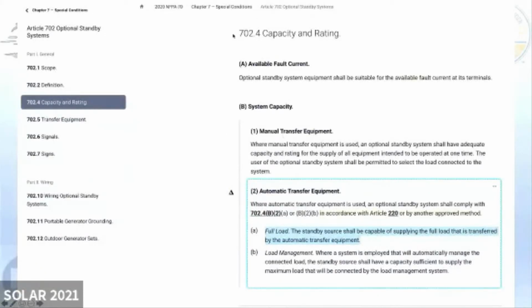And so we've got Article 702, and 702 is optional standby systems. If you call it an automatic transfer switch, or automatic transfer equipment, and then it says you have to back up the full load.